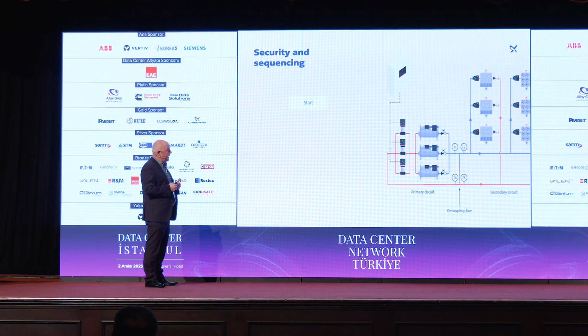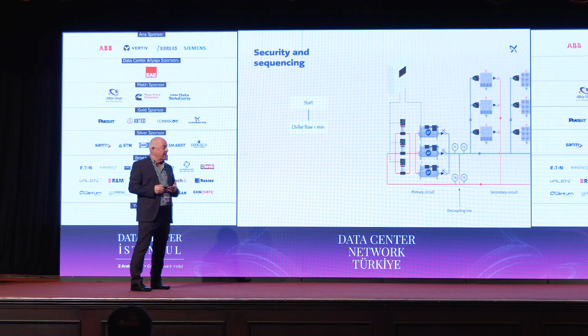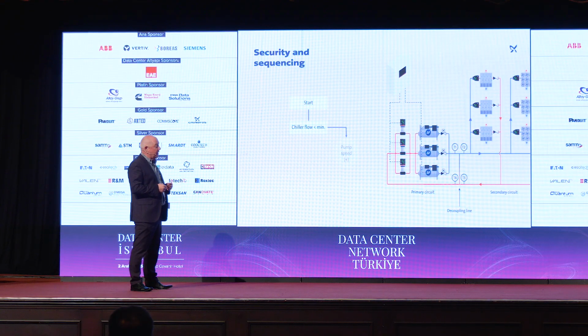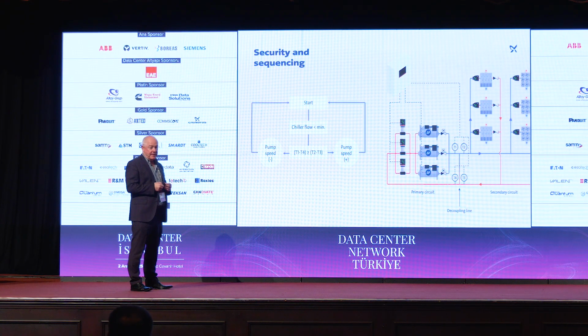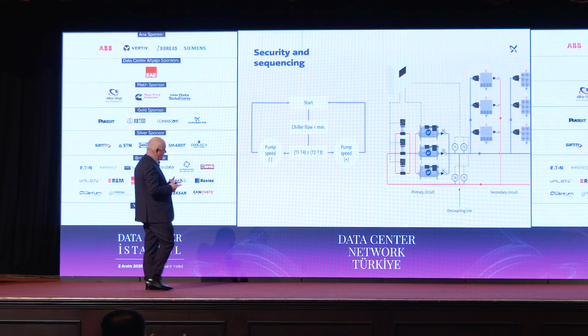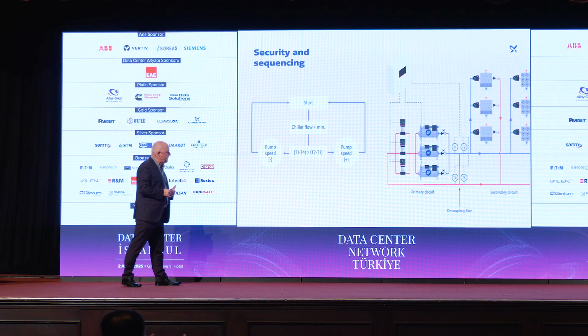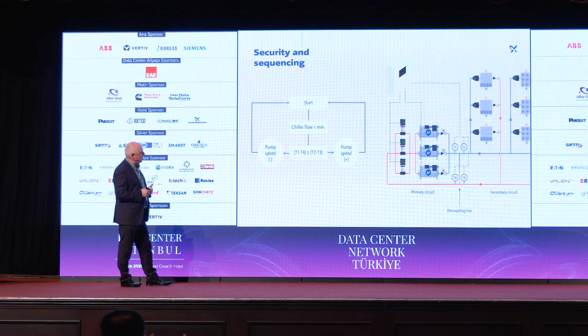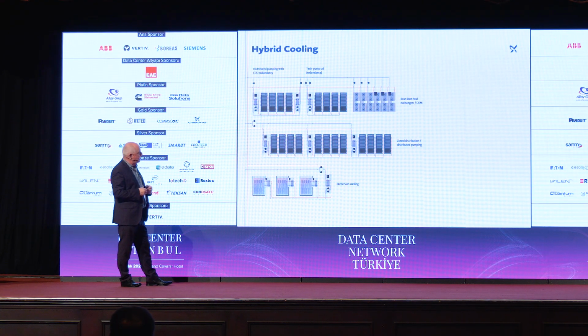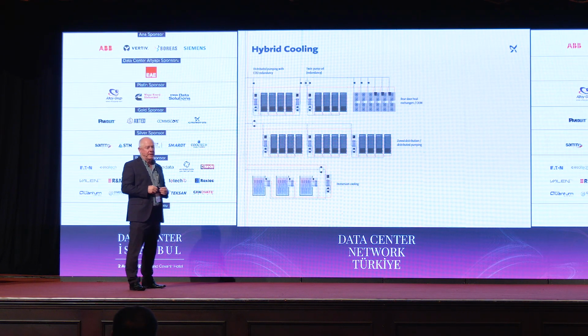So if you look at the sequencing and security, which is really, really important, we make sure that we meet the minimum flow of the chiller. And after that, we start looking at what the load is on the secondary side and meet that load. So it's happening constantly in real time. And as the system is operating, this constantly happens. Now we do rotate the pumps, we do different things like that as well, so we're not having the one pump running all the time, or we have our redundancy built in, but we just keep that system running as efficiently as possible.